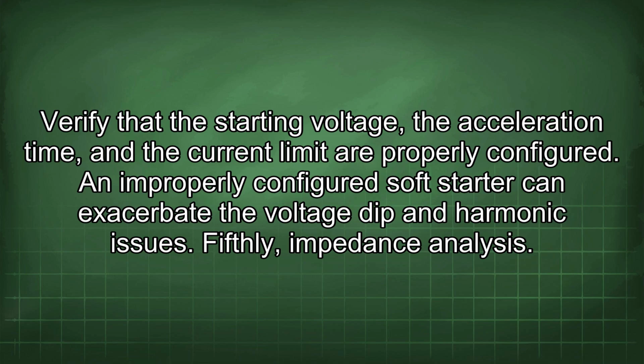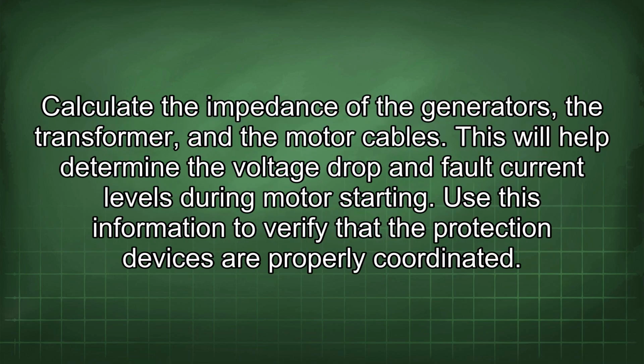Fifthly, impedance analysis. Calculate the impedance of the generators, the transformer, and the motor cables. This will help determine the voltage drop and fault current levels during motor starting. Use this information to verify that the protection devices are properly coordinated.